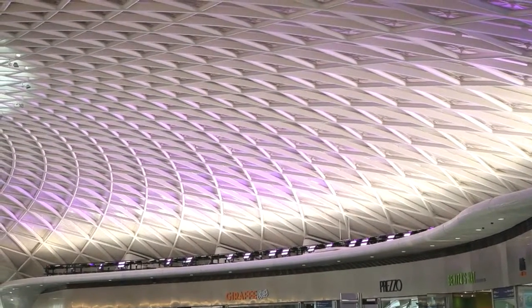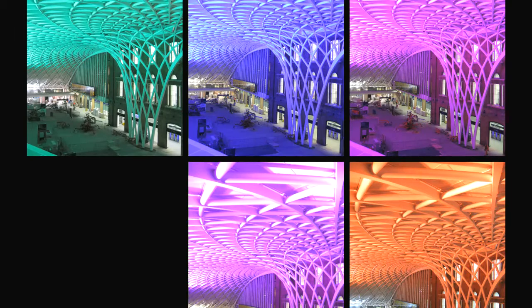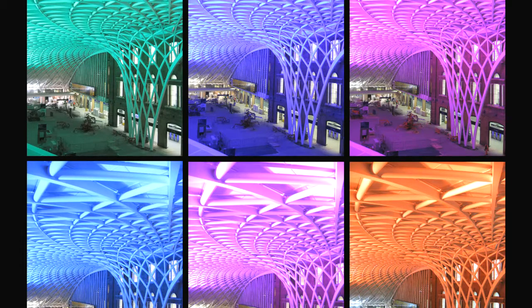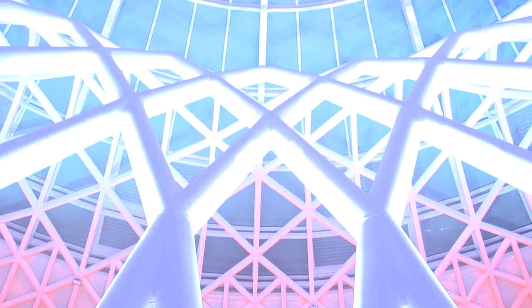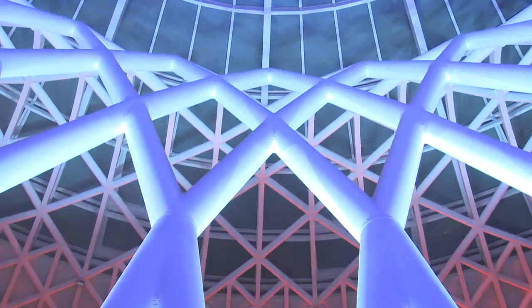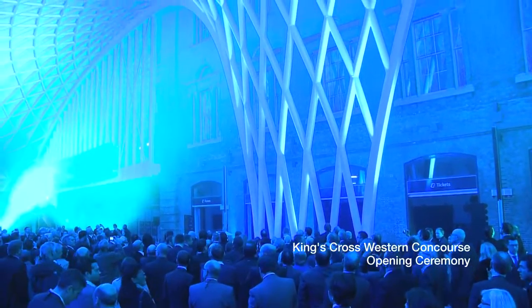The other thing we wanted to do — the building was white, so we wanted to add some colour. What we did was add DMX controlled lighting. Not just blue, which was the original thought to have a contrast against the yellowish bricks of the Western Range building, but full colour. To get the even flow of colour over the roof was quite difficult. We used some quite complicated lighting modelling software to do that, but in the end we had to finally tweak the aiming angles to give the perfect, beautiful flow of light.